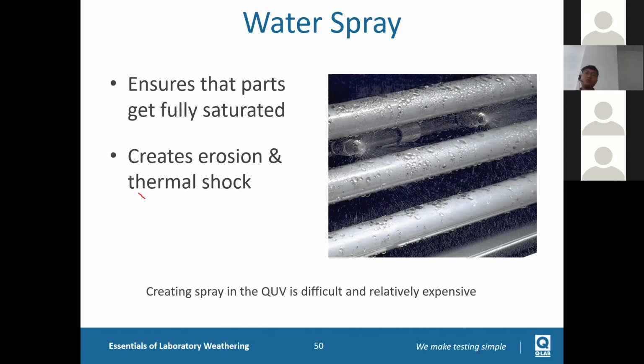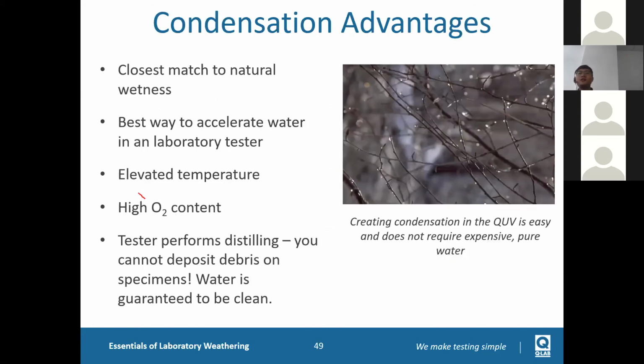That's because if you do water spray, the spray water must be DI water. You need a machine to generate the DI water. But if you only do condensation, then you don't need the DI water system. You can use it if you have it - is that perfect? But if you don't have it, you don't need to buy it additionally because it's condensation.